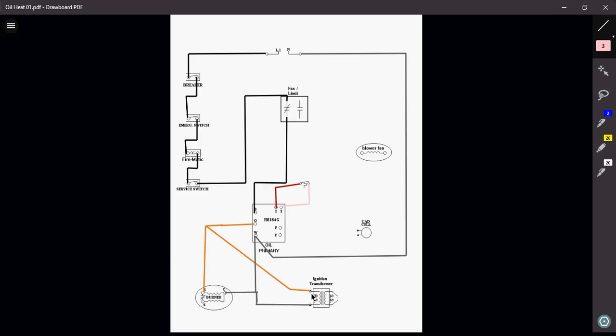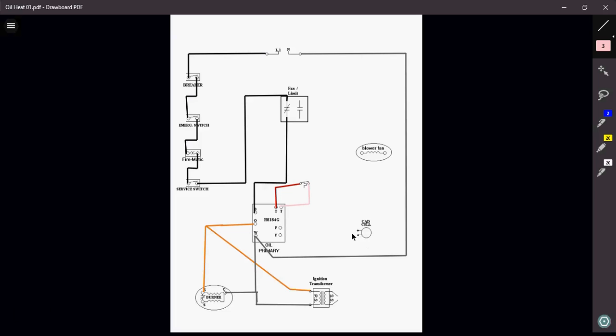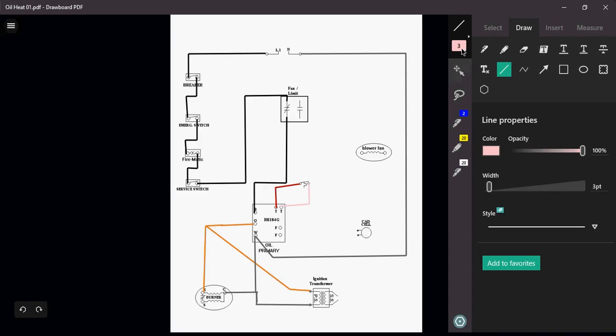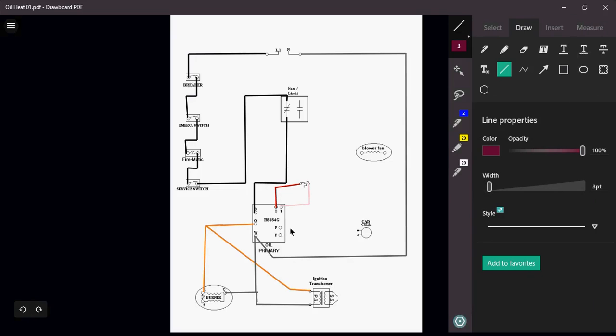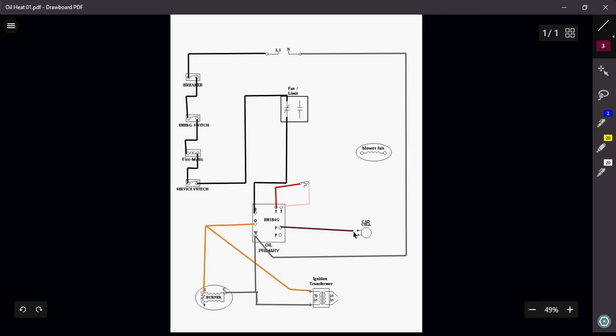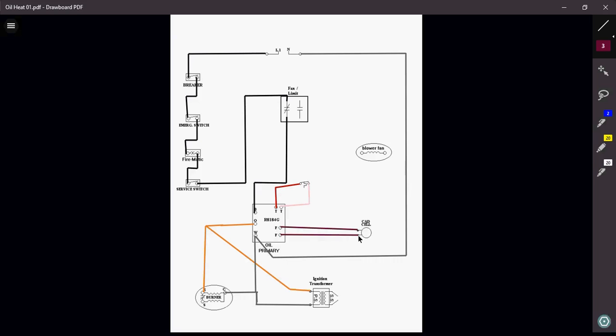So, the last thing I have, or the last two things that I have here, is I have a CAD cell. The CAD cell is nothing more than a flame sensing device. So, once my burner lights, my CAD cell will actually see the flame. It will see the light of the flame. And it will send a signal back to the primary control saying that the actual burner actually did light. So, the CAD cell is really simply wired by two wires that just get connected right back to the FF terminal. It bases its resistance reading. When the flame lights, the resistance of the CAD cell actually drops. And when that happens, it sends that signal back to the primary control, and it tells the primary control that the flame actually did light.